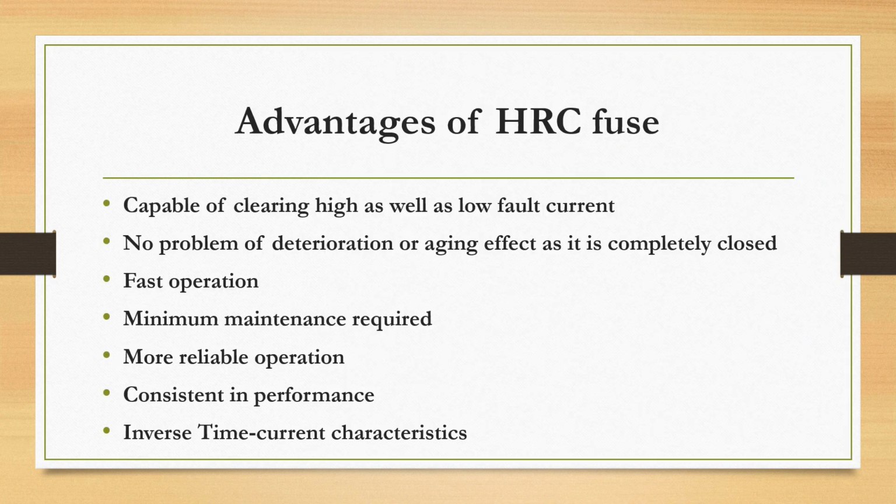From this complete discussion, you can easily list out the advantages of this HRC fuse. So let's list them out one by one. First one is, it is capable of clearing high as well as low fault current. Your HRC fuse has no problem of deterioration or aging effect as it is completely closed inside the cartridge. It is very fast in operation and has a special characteristic, inverse time current characteristic. So depending on that, the operation is very fast.